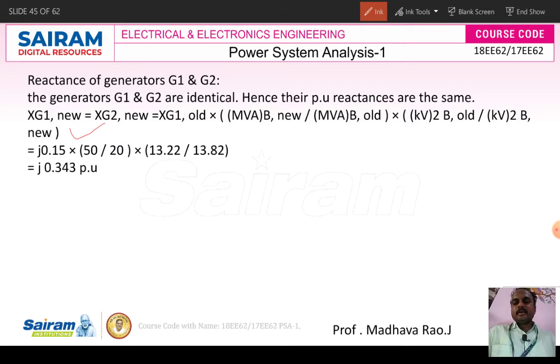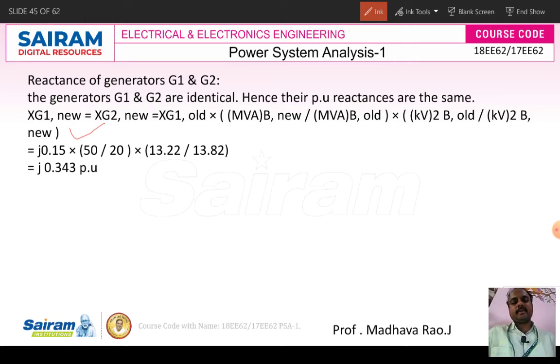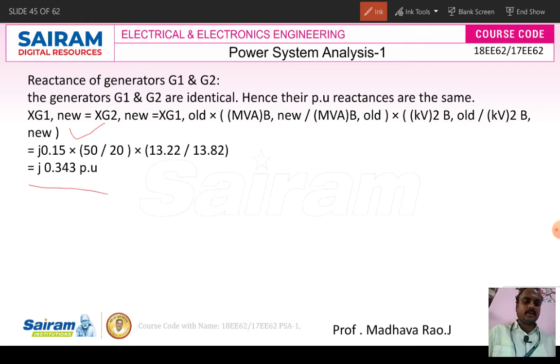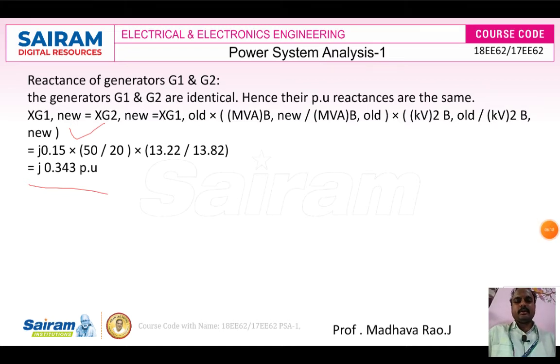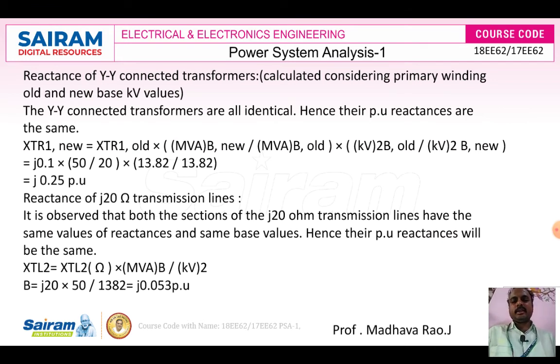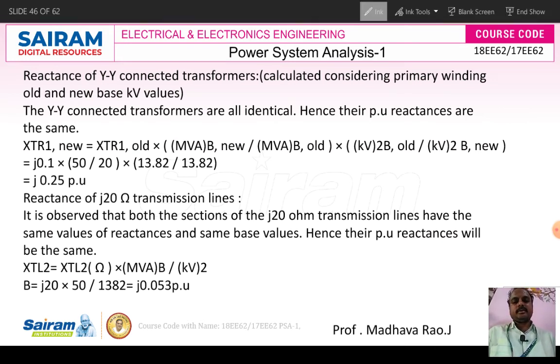Using this formula, we substitute the old reactance value, MVA_base_new, MVA_base_old, kV²_base_old, and kV²_base_new. Finally, we get j0.343 per unit for the reactance of generator 1 and generator 2.